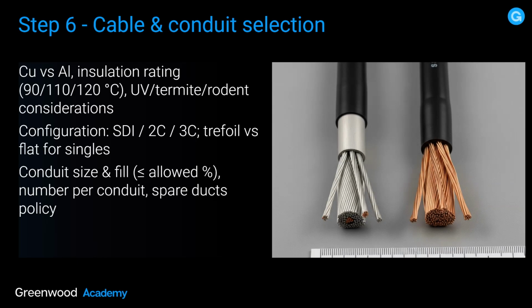Conduit size and fill, less than or equal allowed percentage, number per conduit, spare ducts policy. So obviously with cable and conduit, it is all about friction. You're talking about multiple cables in conduit. You're talking about the friction of the cables against each other. You're talking about friction of the cables against the internal walls of the conduit, how many bends there are, what's the allowable space, what is best practice, and these things, again, have to be worked out well before you get to site.